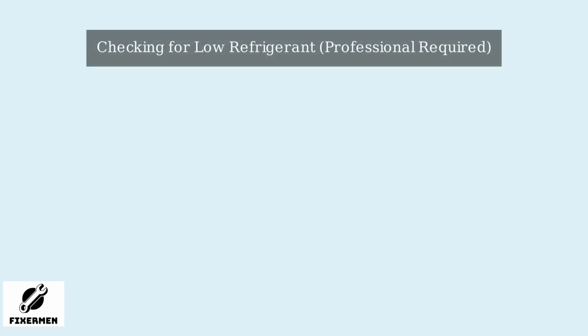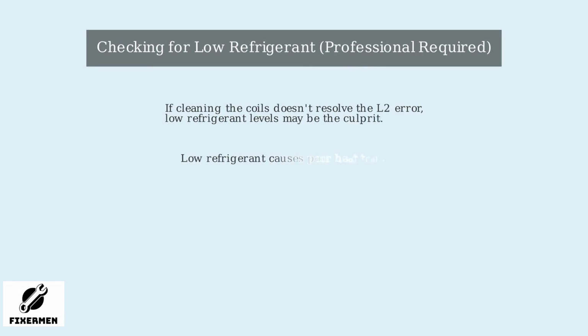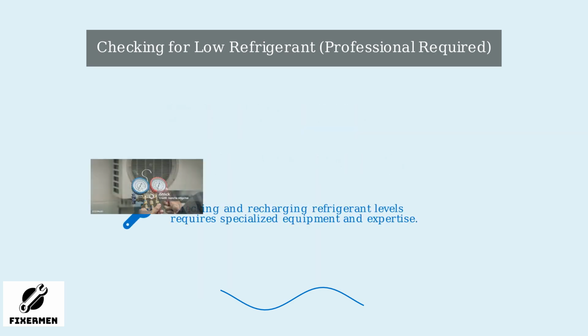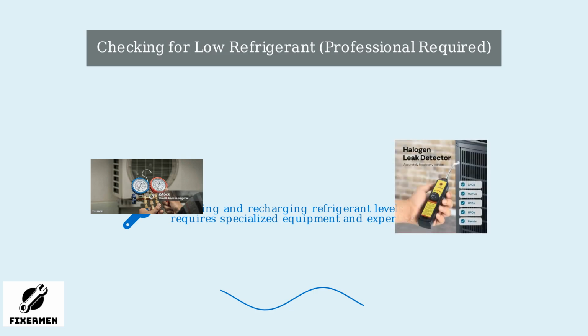If cleaning the condenser coils doesn't resolve the L2 error, low refrigerant levels may be the culprit. Low refrigerant causes poor heat transfer in the system, leading to overheating in the outdoor unit and triggering the L2 protection. Checking and recharging refrigerant levels requires specialized equipment and expertise, such as manifold gauge sets used to measure system pressures. Technicians also use leak detectors to find any refrigerant leaks that could cause the low levels.